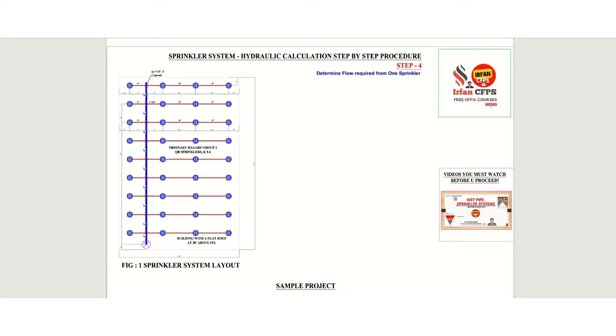Let us start step 4. In step 4, we will determine the flow required or the minimum amount of water required from each sprinkler. There is a formula to calculate the flow from each sprinkler: q equals area into density.